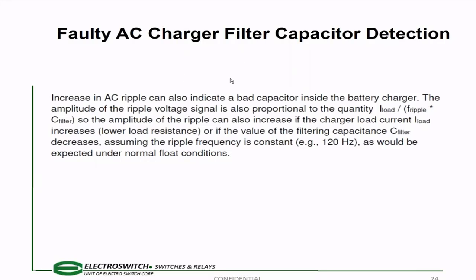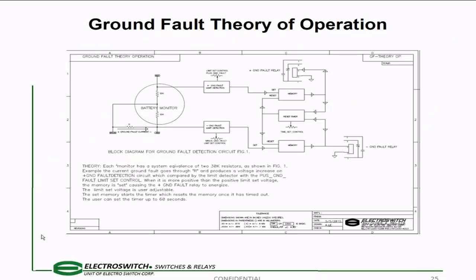Faulty AC charger filter caps. You go and check your battery because you have the high impedance alarm. You go check your battery, there's no corrosion, no open cell, no loose strap. That sends you to the AC filter caps and you find out that your AC capacitors have an issue. Typically, a utility down in the south just did this, and that's exactly what was wrong, so they replaced the filter caps. And they usually last 7 to 10 years. I mean, you guys would know that better than me. Anyway, I'm preaching to the choir.